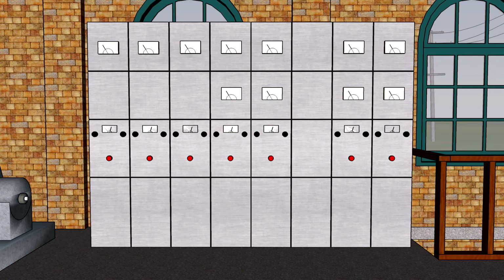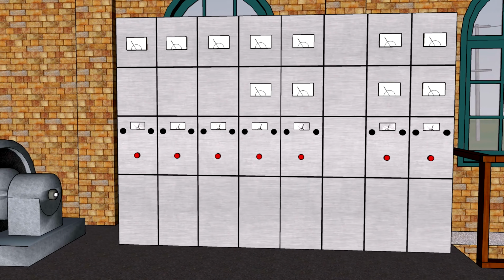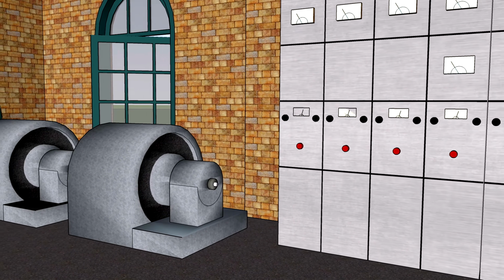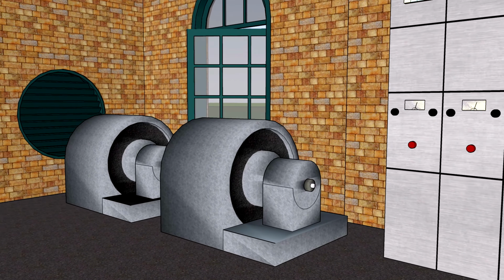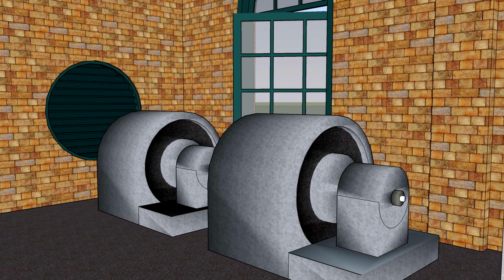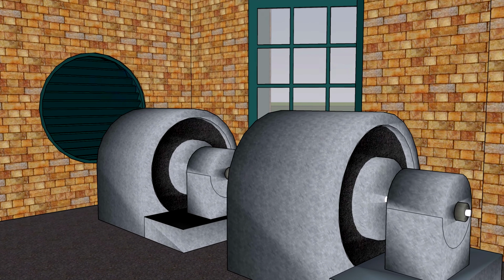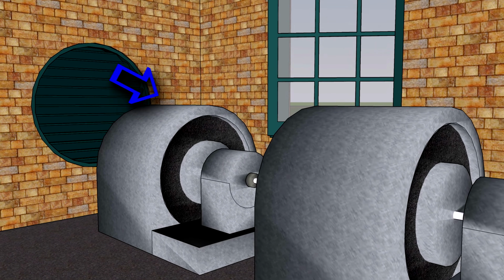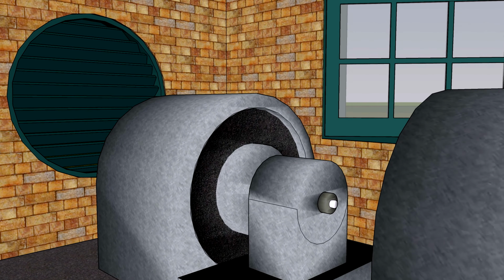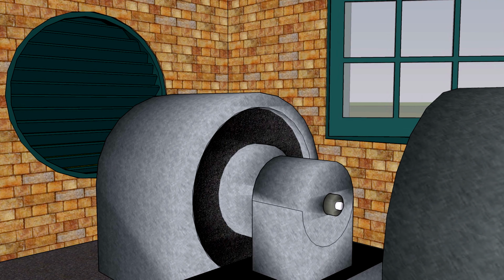All of the wiring for the switchboard once again came in through an opening in the main floor, beneath and behind the panels. In the northwest corner of the rotary room were 2 3-horsepower Buffalo Forge blower motors. Only one blower was operating at a time, with the second blower being available for backup or maintenance, a cold standby. These blower motors were positioned next to the large 4-foot-wide circular vent on the west face of the substation, where they would take in the external air through the vent and push it at high volume into the airtight basement below, via openings in the main room floor directly beneath the blowers. The air would be chilled to some degree by the cooler temperatures of the subterranean basement, before being pushed up through the openings in the main floor for the transformers, rotary converters, and oil switches, thereby keeping them immersed in a stream of cooler air.